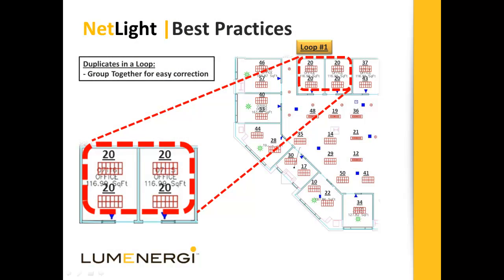In the event that more than one ballast share the same DALI address on a single loop, otherwise known as duplicates, install them near each other for easy correction during commissioning. In the example shown here, 4 ballast address 20 on loop 1 are installed in adjacent offices for ease of commissioning.